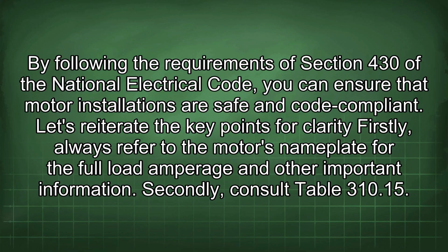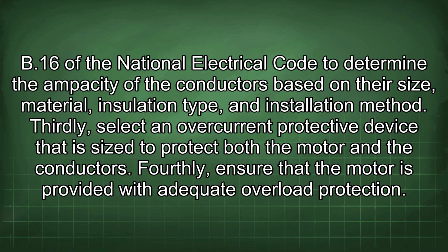Firstly, always refer to the motor's nameplate for the full load amperage and other important information. Secondly, consult Table 310.15(B)(16) of the National Electrical Code to determine the ampacity of the conductors based on their size, material, insulation type, and installation method. Thirdly, select an overcurrent protective device that is sized to protect both the motor and the conductors.